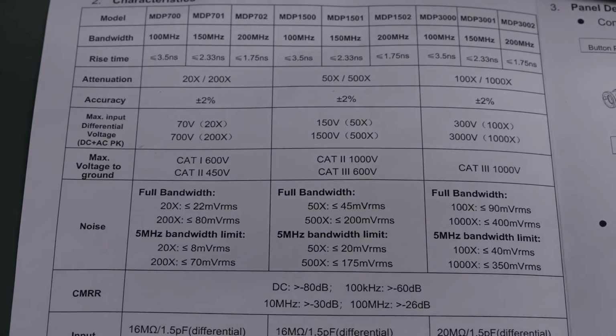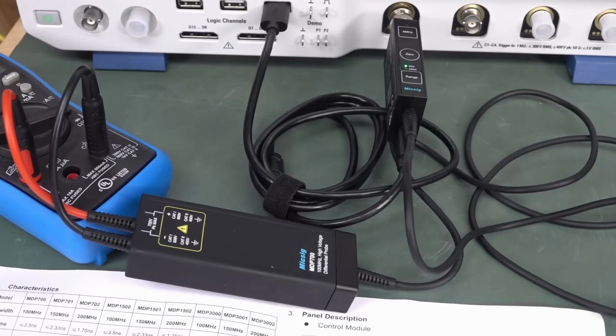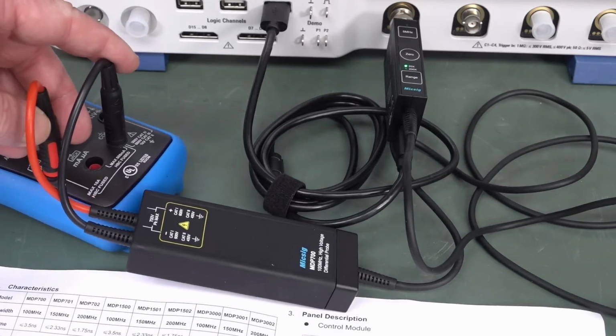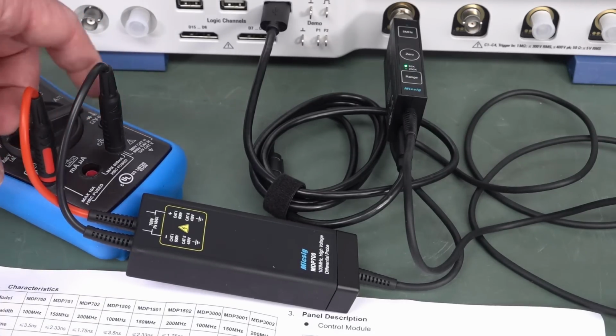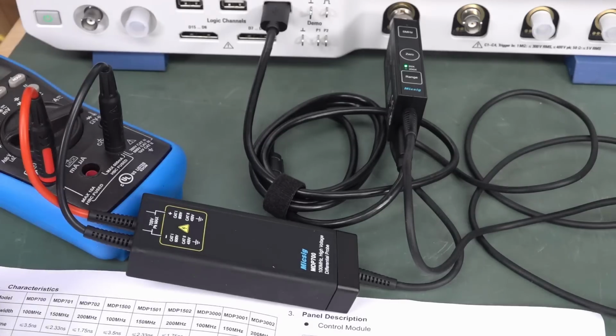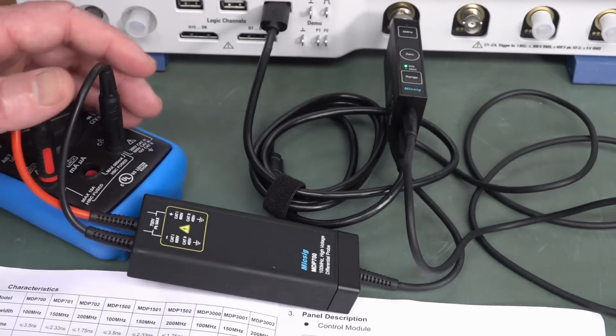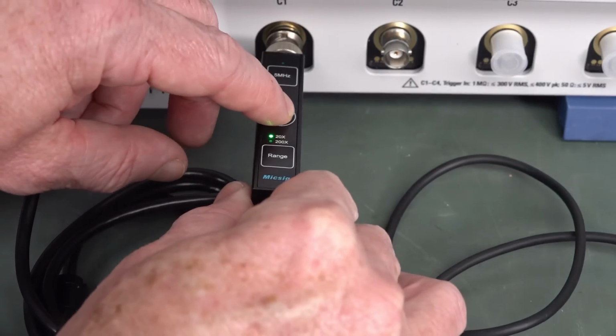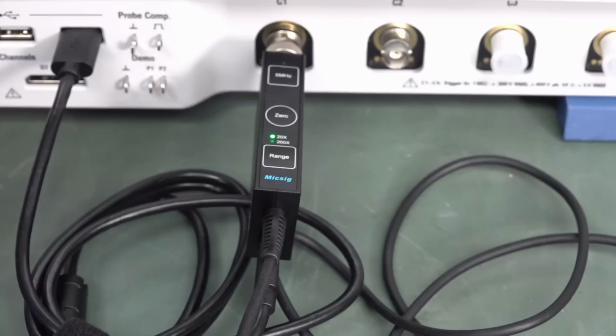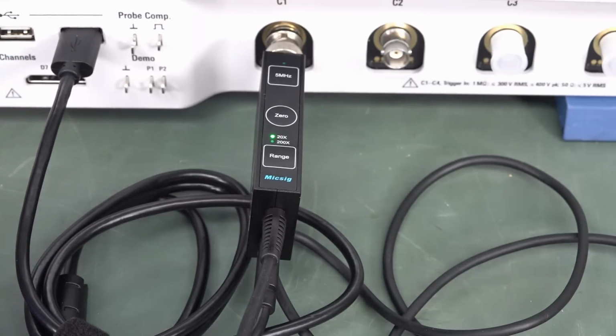So what we're going to do is zero this, so we need to short the input out. You can't do that unless you've got a banana to banana, so you can put it on the current range of your meter, no worries. So we've shorted out our input here, and then we press our 0 button, and boop, you hear 1 beep, it's fine. If you hear 3 beeps, then it's failed for some reason.